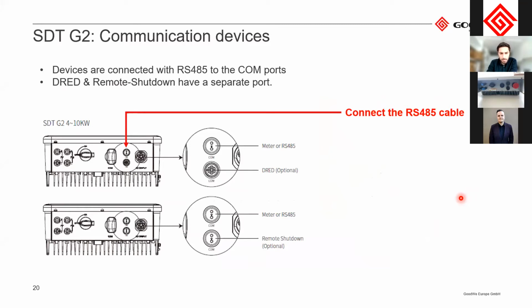The maybe more tricky part is the communication devices. So in case you want to connect a meter or connect it to a second inverter that then goes to a data logger, then you will need to connect it to this port here, the upper port. On the lower port, you have this remote shutdown or DRED function, which I will talk a bit more about later.